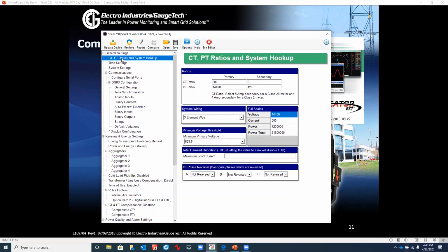It's 14 kV to 120 type PTs, and then you would determine if it's a line to line, neutral type connection. So we would need to go and determine whether it's a 3 element, a 2.5 element, or a 2 CT delta. A 3 element meter configuration requires 3 line to neutral voltages and 3 phase currents to measure 3 phase power accurately.